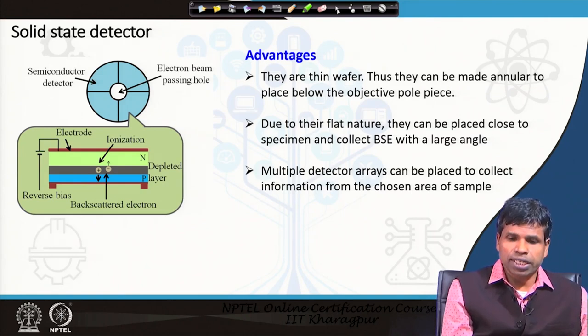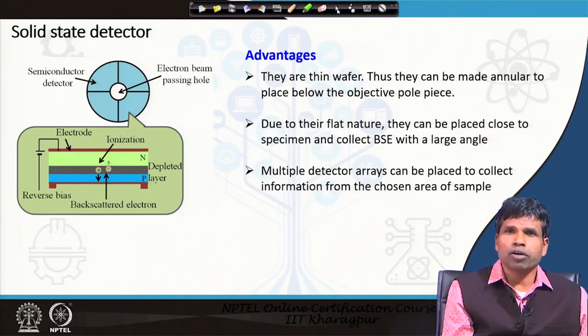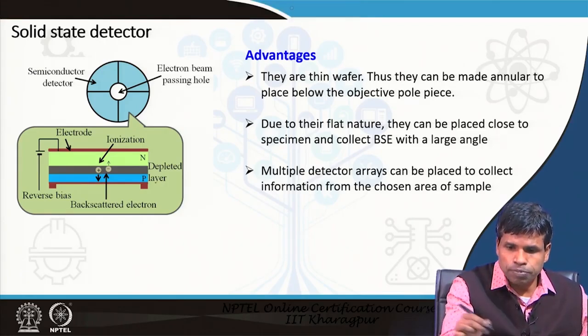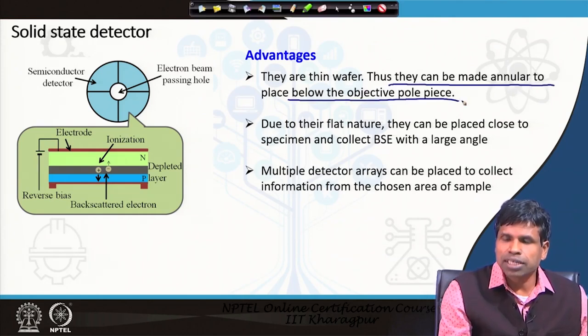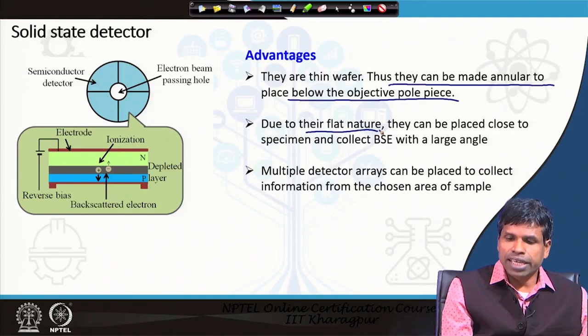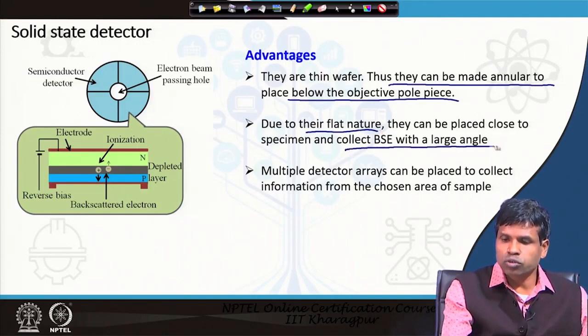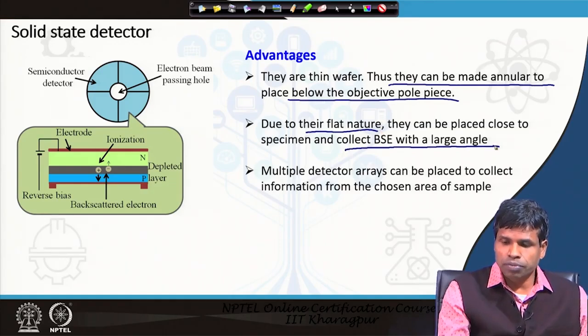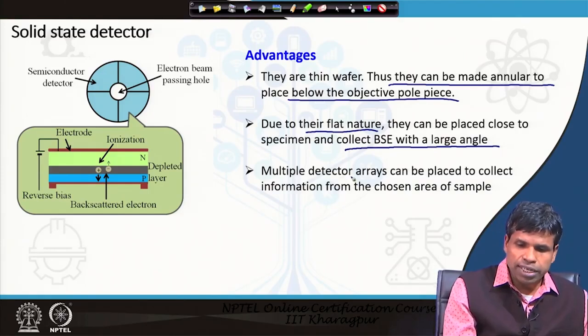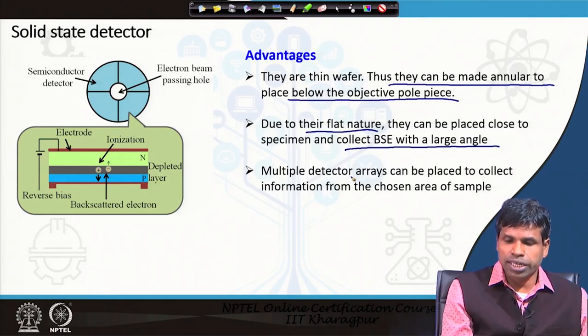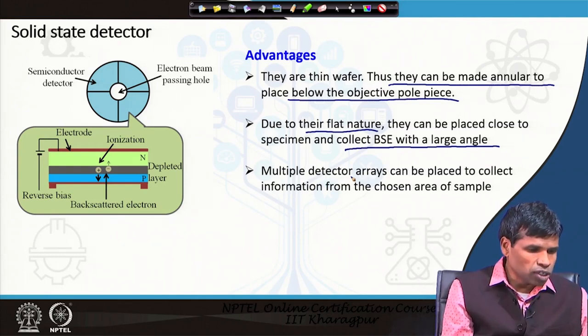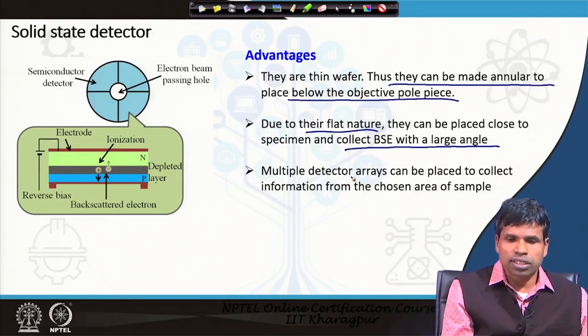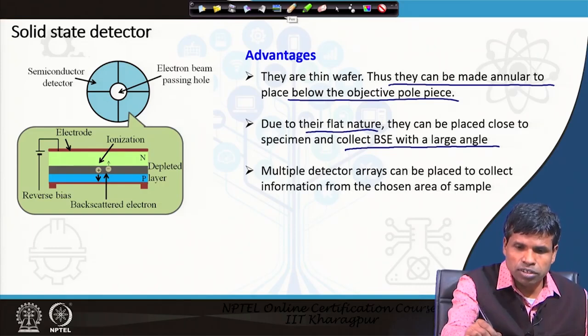These detectors have certain advantages because they are semiconductor wafers in thin wafer form. They can be made annular to be placed below the objective pole piece, and they can be placed close to the specimen to collect backscattered electrons over a large solid angle of almost 2π. Multiple detector arrays can be placed on the detector to collect information from a chosen area of the sample. This solid state detector is what is used in present day scanning electron microscopes.